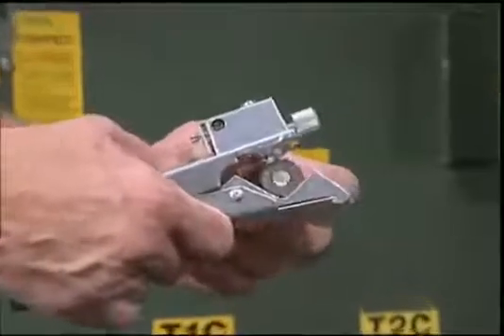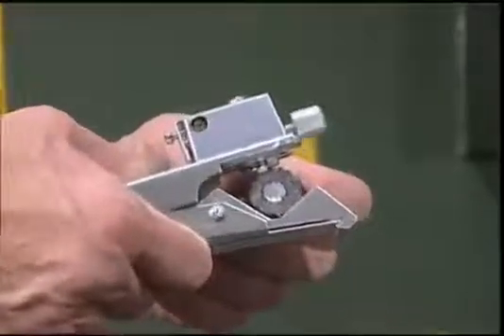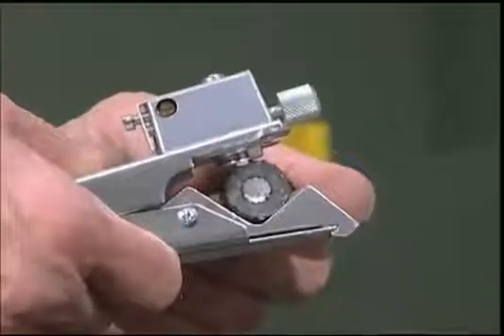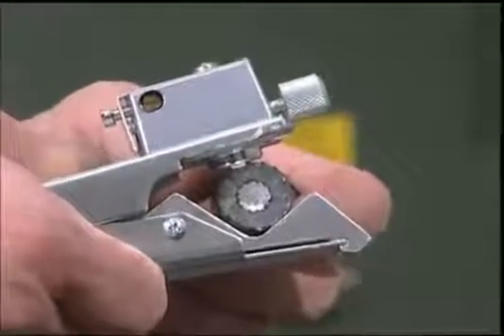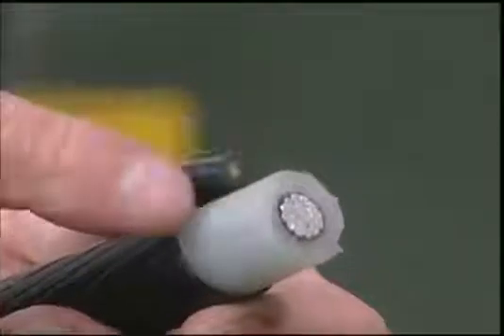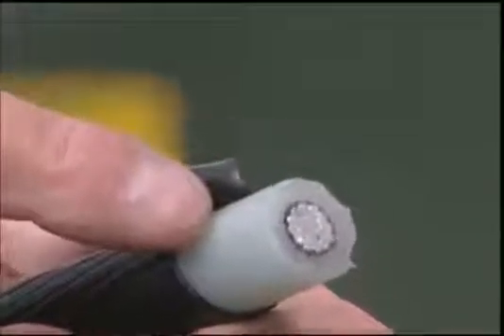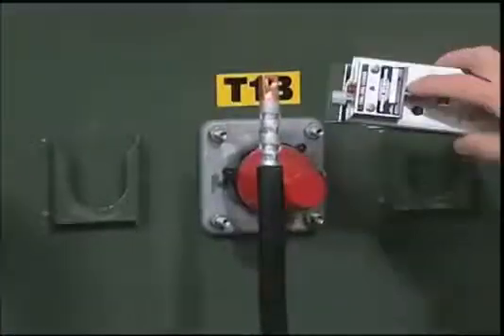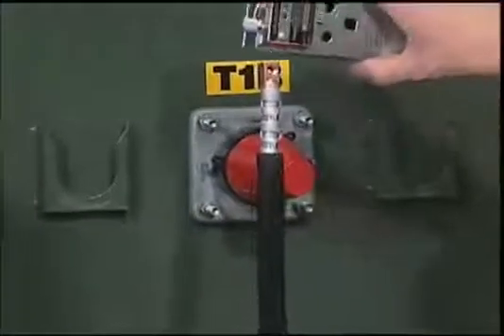Practice setting the depth of cut on the insulation removal tool using a scrap piece of cable. Do a trial insulation shield removal on the piece of scrap. Verify there are no score marks on the insulation. Witness lines are allowable.